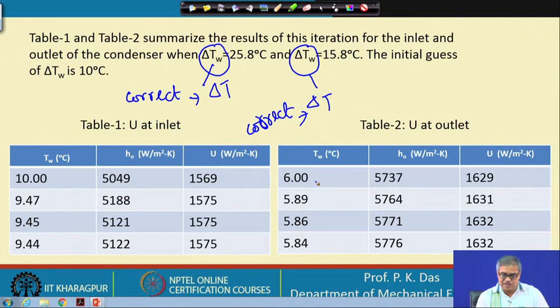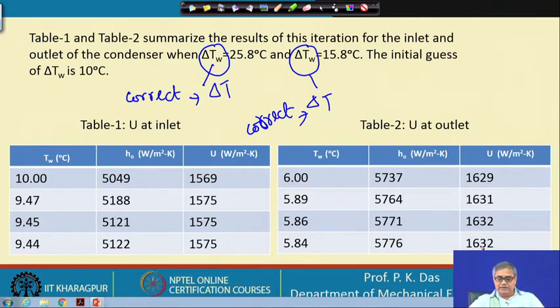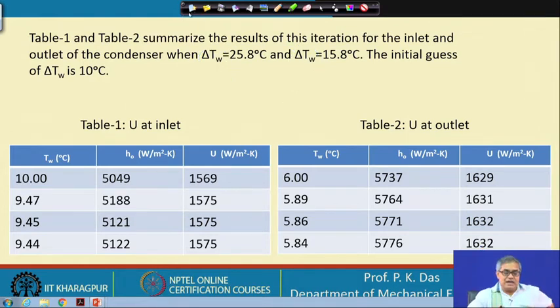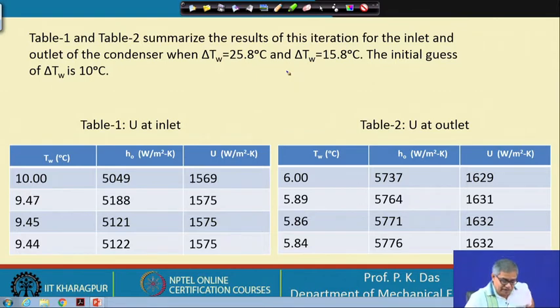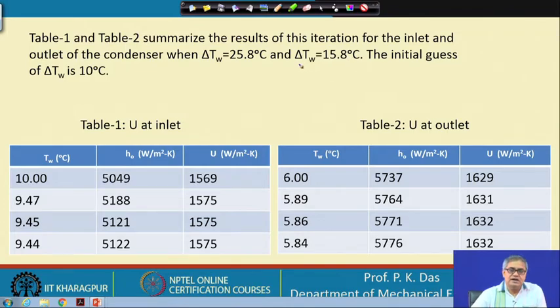Similarly, at the outlet we assume delta T_w = 6°C as the initial guess, perform the same kind of iteration, and ultimately obtain the overall heat transfer coefficient U_outlet = 1632 W/m²K. Knowing U at the inlet and outlet, we calculate the average overall heat transfer coefficient for the entire tube length.